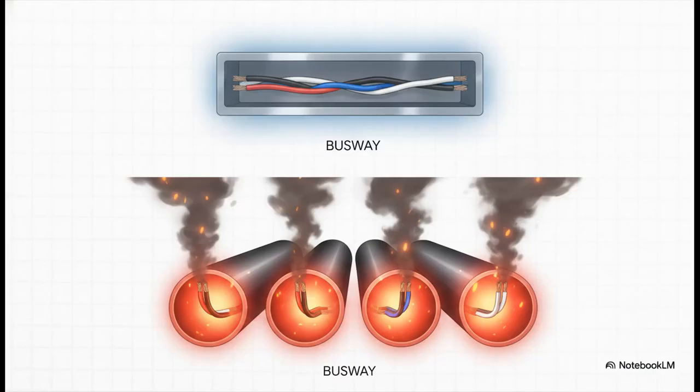And hey, don't forget the classic electrical theory trap. Rule 12-2004 reminds us that if you're running alternating current through any enclosure made of magnetic material, like, say, standard steel, every single conductor of that circuit, line 1, line 2, line 3, and the neutral, must all be run inside together. By keeping them all bunched together, their magnetic fields actually cancel each other out.